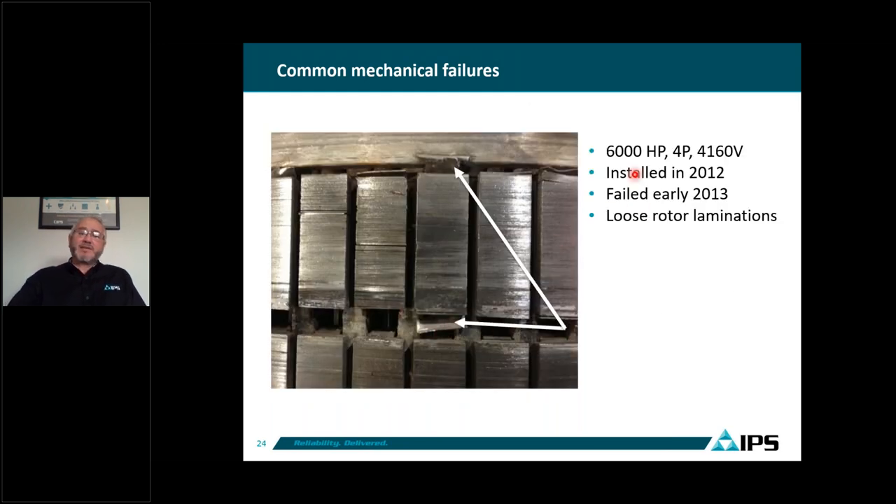Another example is a 6,000 horsepower, 4 pole, 4,160 V motor installed in 2012 that failed early in 2013. That was loose lamination. Rotors with loose laminations on two, four, or six pole machines are not acceptable. We sent a report to the OEM and their answer was that it was cosmetic — but loose laminations at high speed is just a matter of time before they crack, fly out, cut the coil or stator board, and cause catastrophic failure.